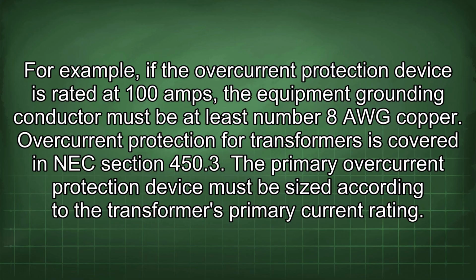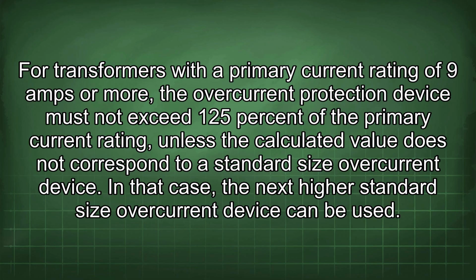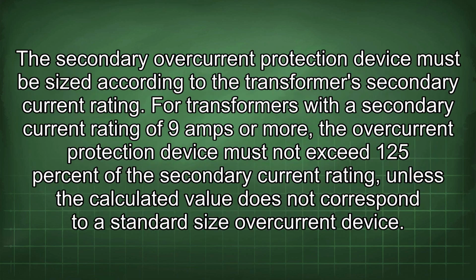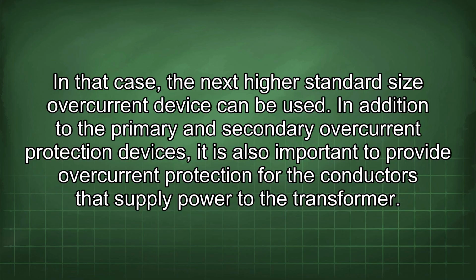The primary overcurrent protection device must be sized according to the transformer's primary current rating. For transformers with a primary current rating of 9 amps or more, the overcurrent protection device must not exceed 125% of the primary current rating, unless the calculated value does not correspond to a standard size overcurrent device. In that case, the next higher standard size overcurrent device can be used. A secondary overcurrent protection device must be sized according to the transformer's secondary current rating. For transformers with a secondary current rating of 9 amps or more, the overcurrent protection device must not exceed 125% of the secondary current rating unless the calculated value does not correspond to a standard size overcurrent device. In that case, the next higher standard size overcurrent device can be used.